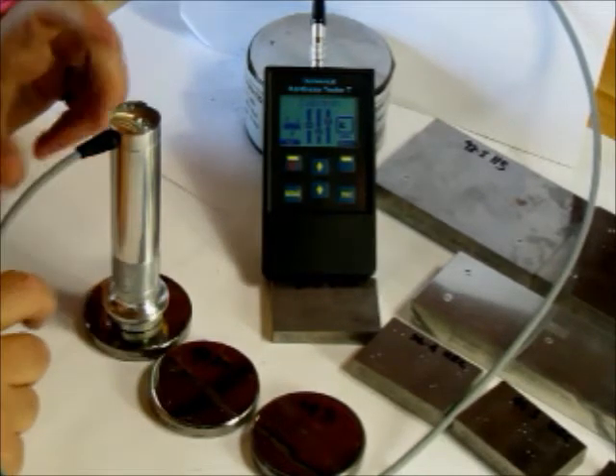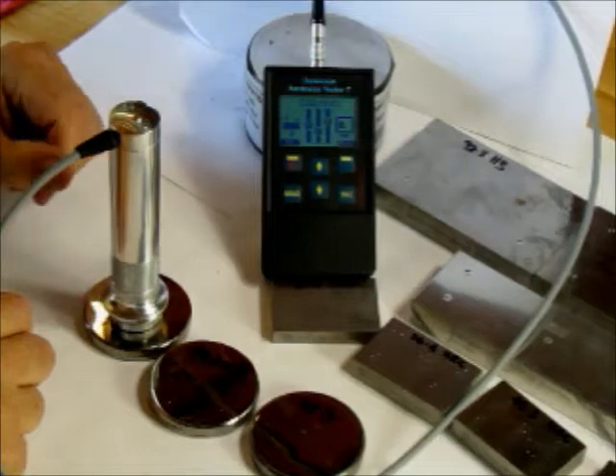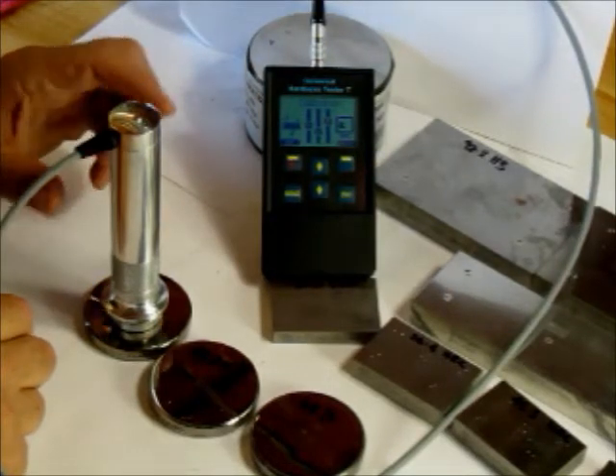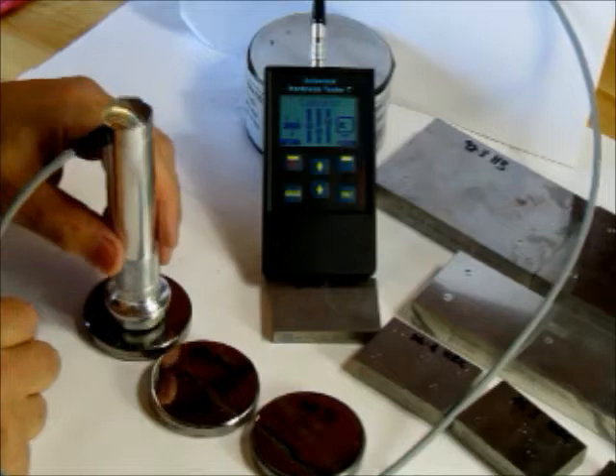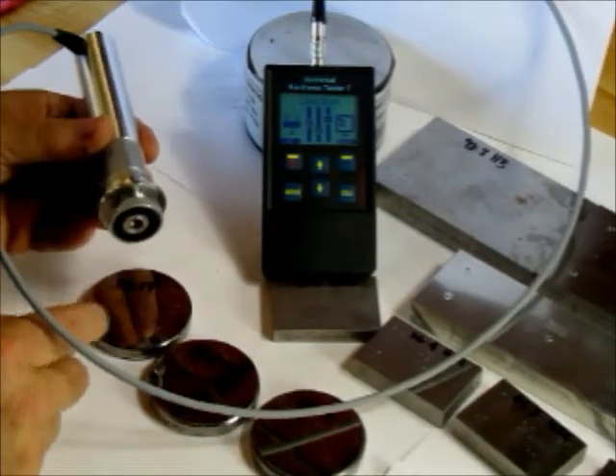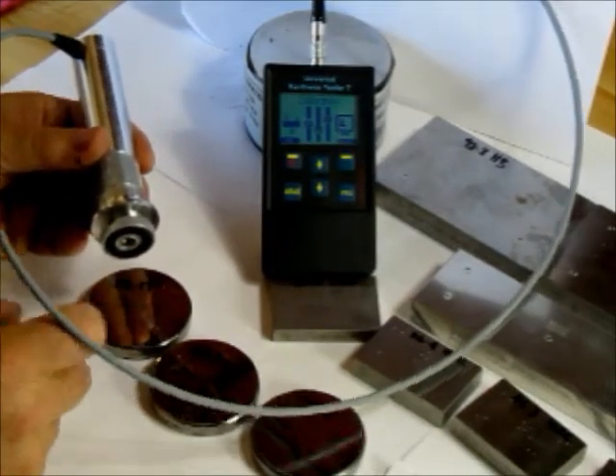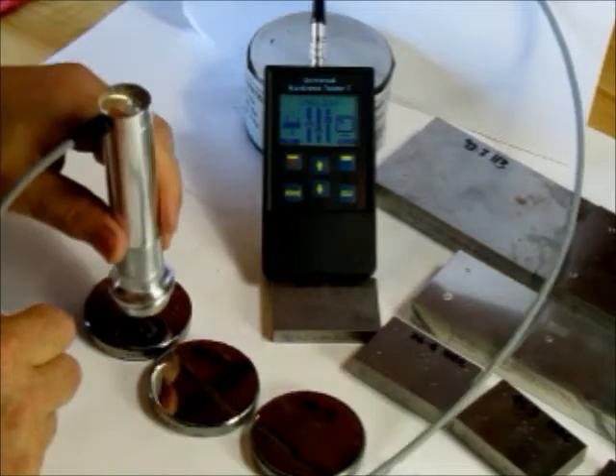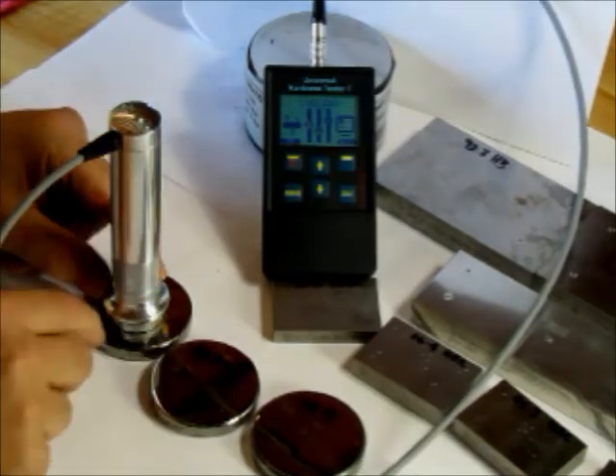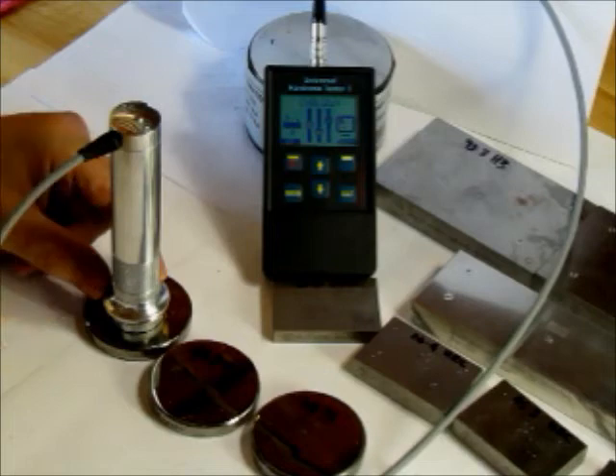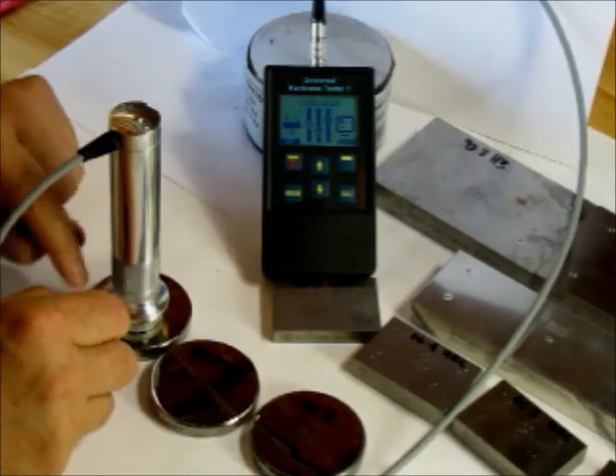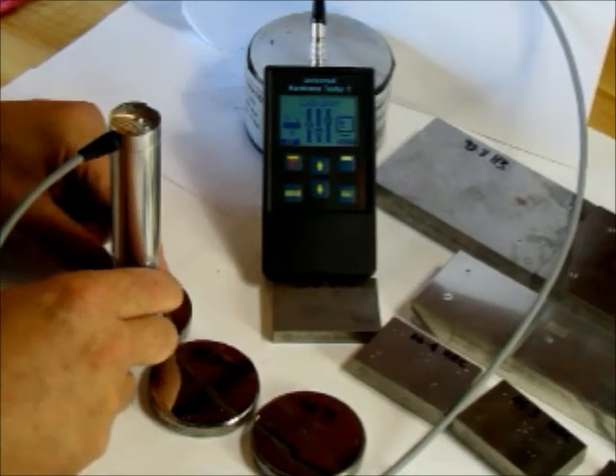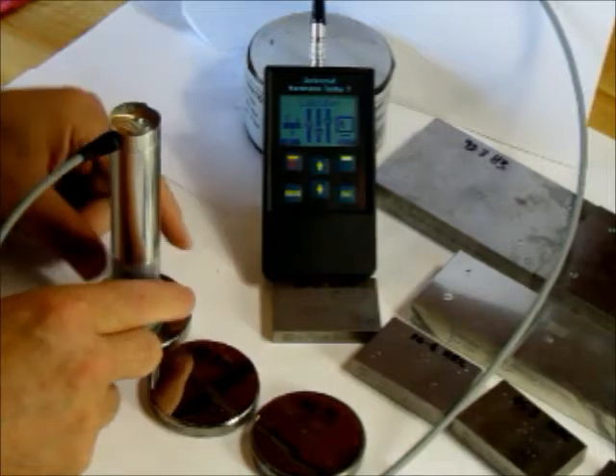So this allows us to keep it very steady because ultrasonic testers of course are all based on the principle of the diamond tip, which is a Vickers diamond going onto the part, vibrating at a very, very high frequency. So we've got to make sure that our probe is perpendicular to the part. It can be of course in any orientation, even upside down, but when the test is done it's going to be perpendicular, and again the motion pushed down and so on.